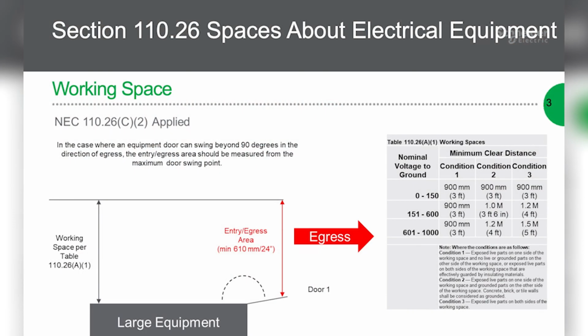You know, Toby, a graphic or illustration might help us with this visually. As we look at the slide on the screen now, we have an example using large equipment, because large equipment would have the largest door sizes that might protrude into the working space. We know we have a requirement that doors must open a minimum of 90 degrees, but in many cases equipment doors will open further than that.